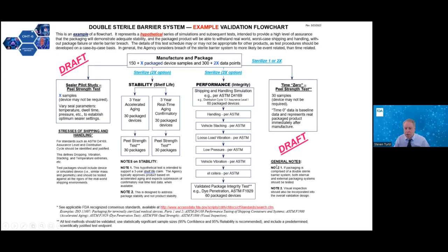Two notes in the bottom right-hand corner. These are valuable. If packaging is comprised of a double sterile barrier system, both internal and external packaging systems should be tested. So if you've got a double sterile barrier system, you can't just test one of them. You have to test them both. And if the testing is conducted on just one, then special labeling has to go on there to indicate to the end user that only one of the barrier systems is validated to be a sterile barrier system.